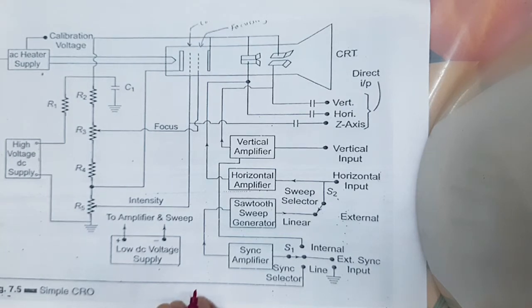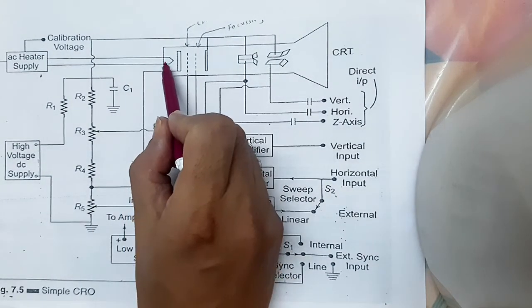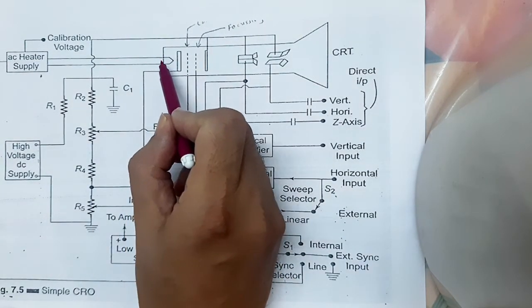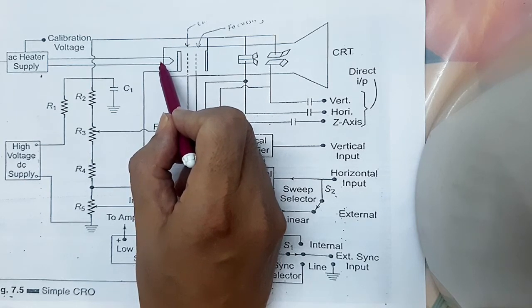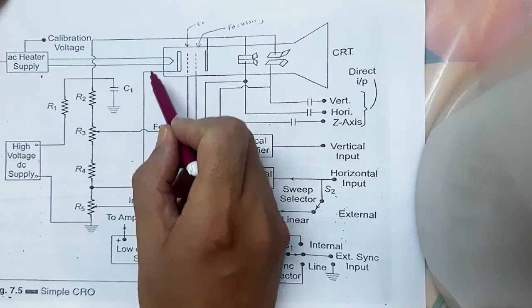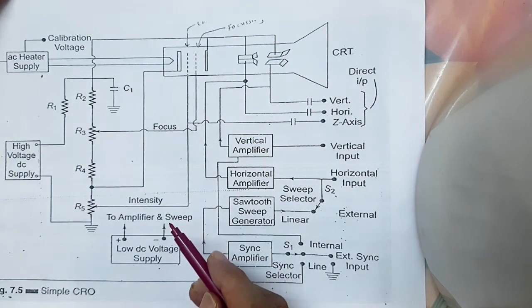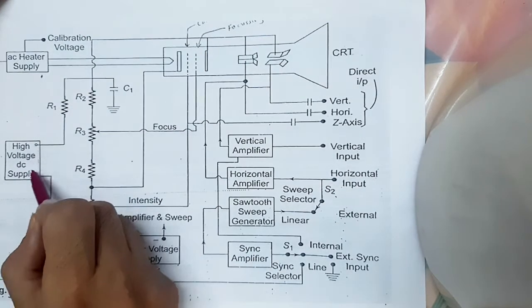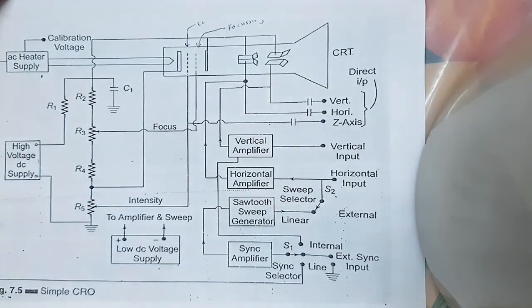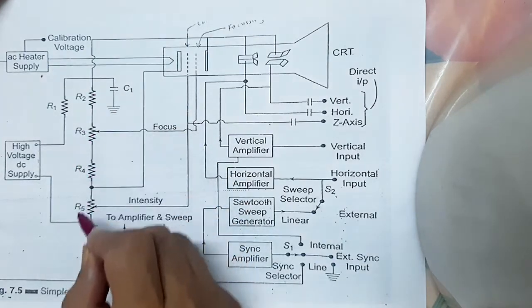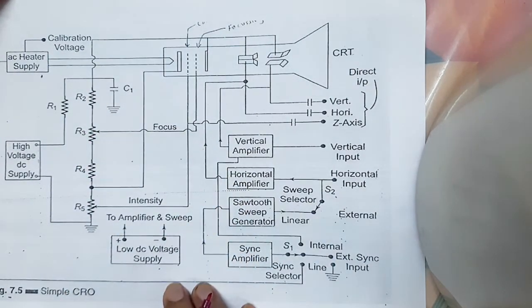The AC filament supplies power to the CRT heaters — this is our heater. This also provides an accurate AC calibration voltage. CRT DC voltage is obtained from the high voltage DC supply. There is a voltage divider R1 to R5 — R1, R2, R3, R4, R5 — which are the voltage divider circuit.